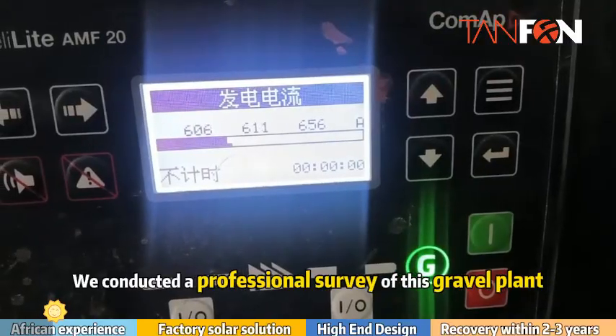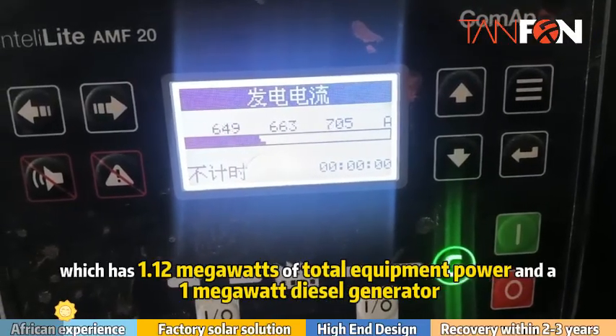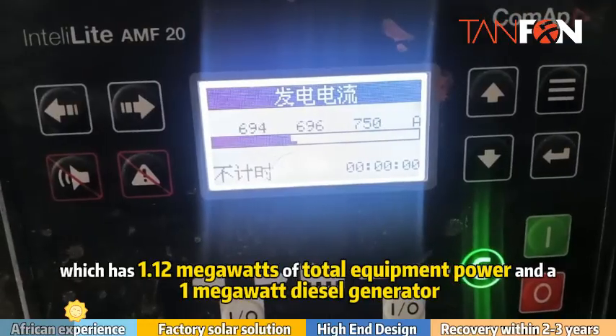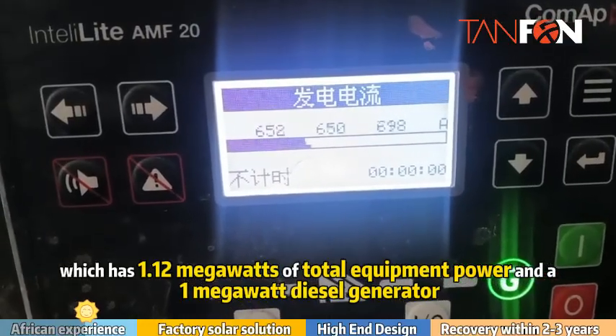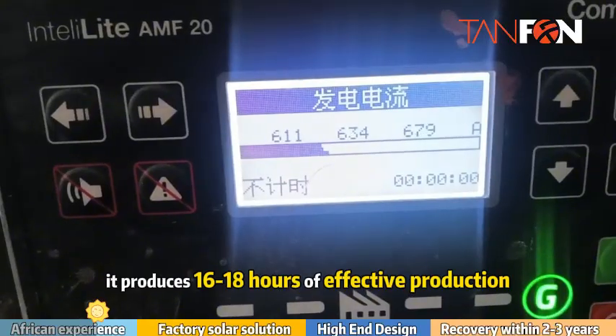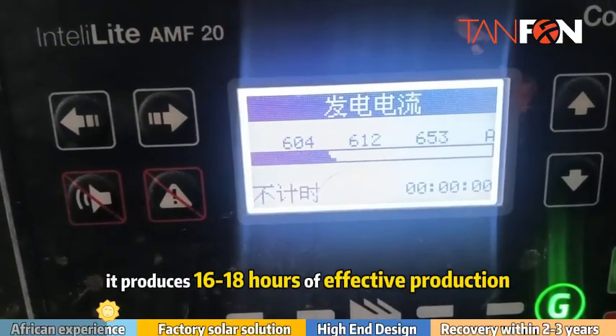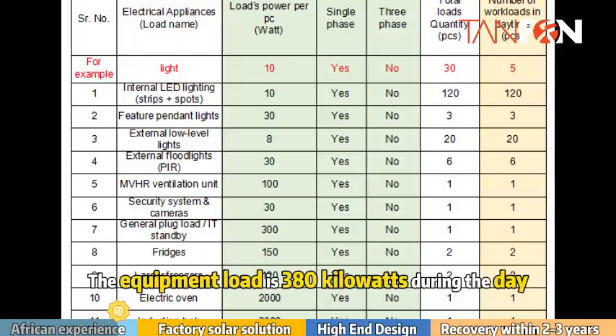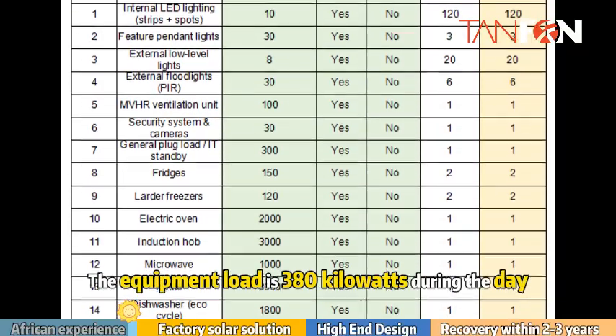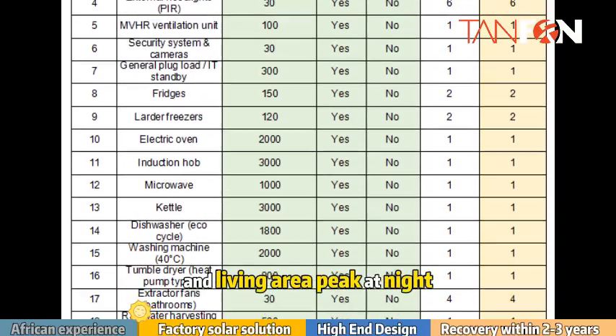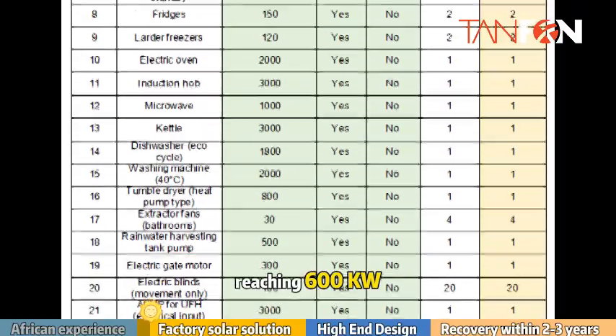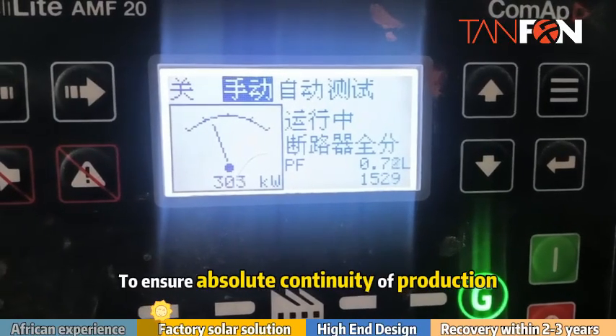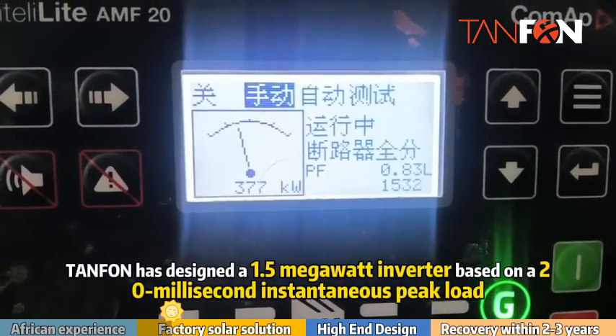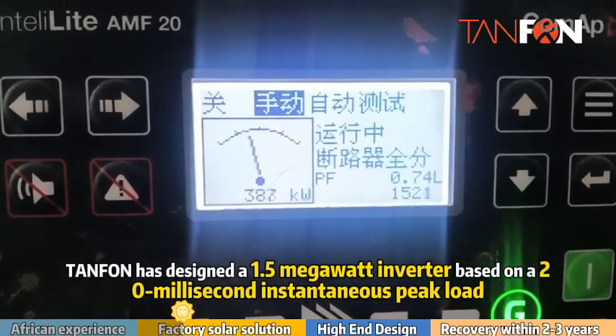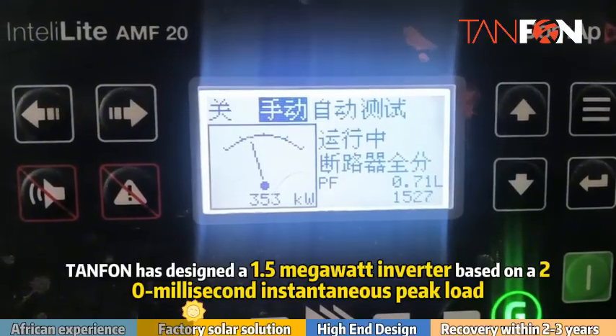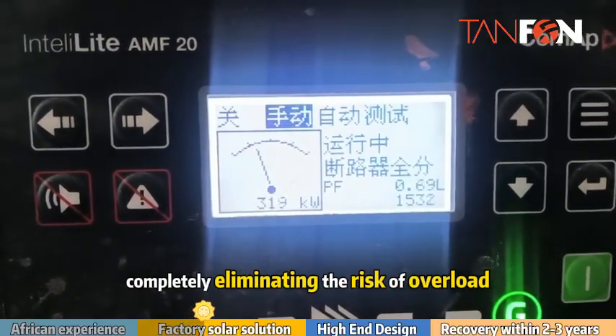We conducted a professional survey of this gravel plant, which has 1.12 megawatts of total equipment power and a 1 megawatt diesel generator, operating 24 hours a day. It produces 16 to 18 hours of effective production. The equipment load is 380 kilowatts during the day, and the equipment and living areas peak at night, reaching 600 kilowatts. To ensure absolute continuity of production, Tanfon has designed a 1.5 megawatt inverter based on a 20 millisecond instantaneous peak load, completely eliminating the risk of overload.